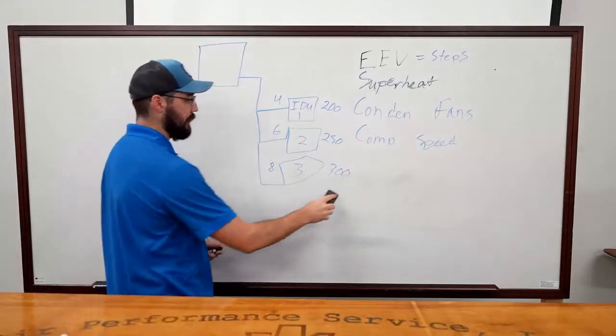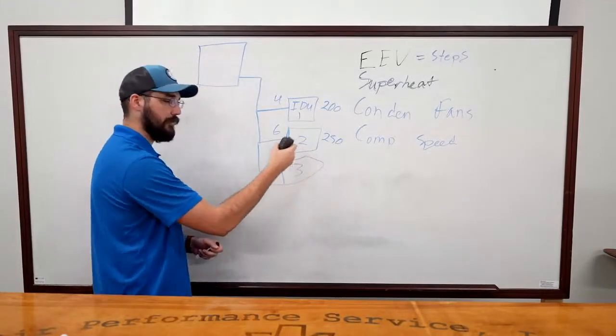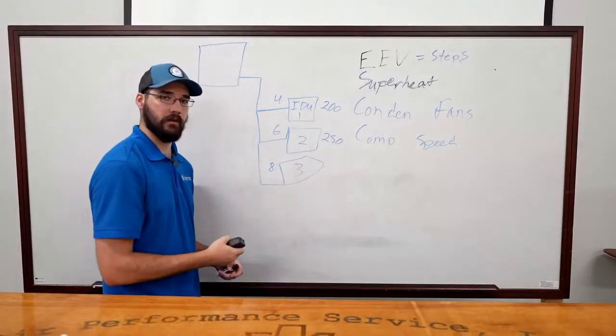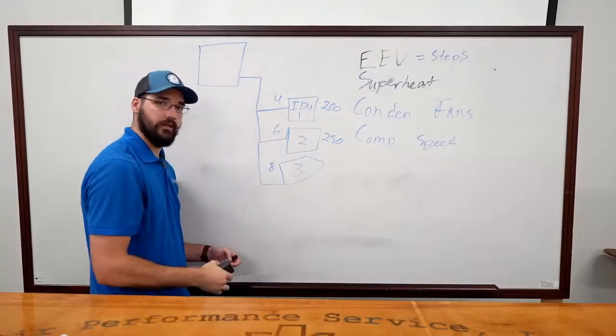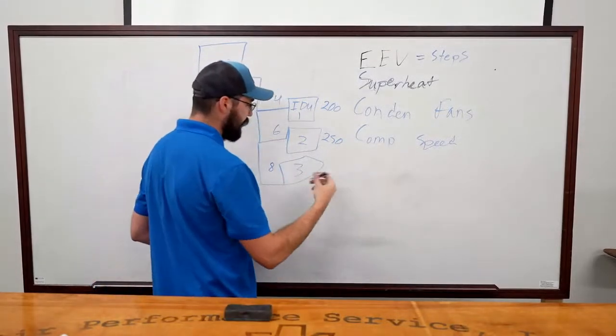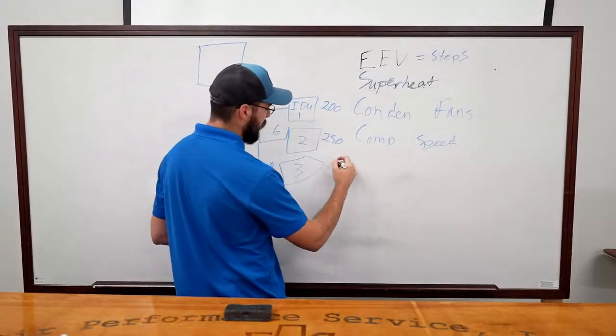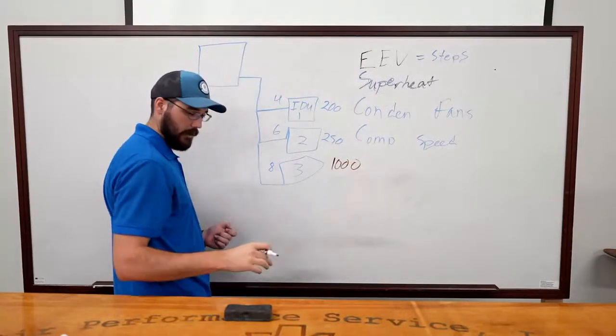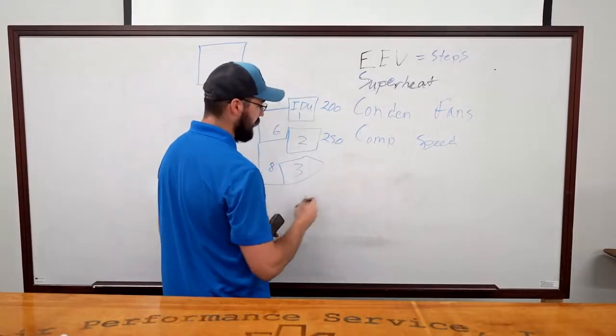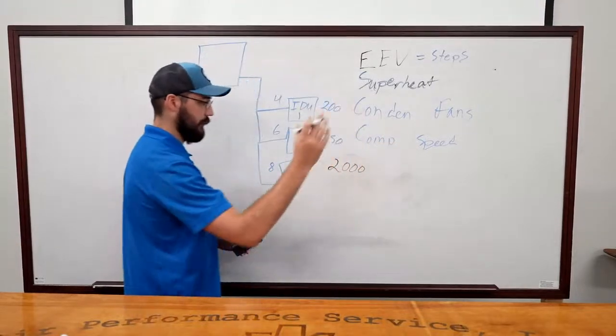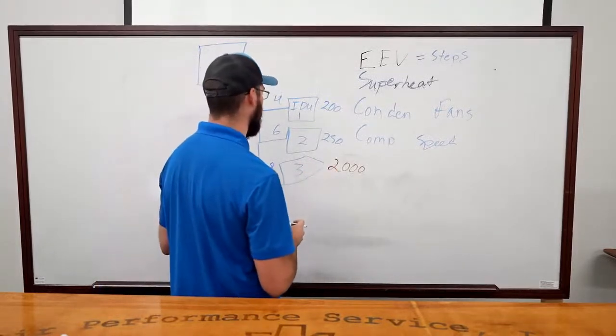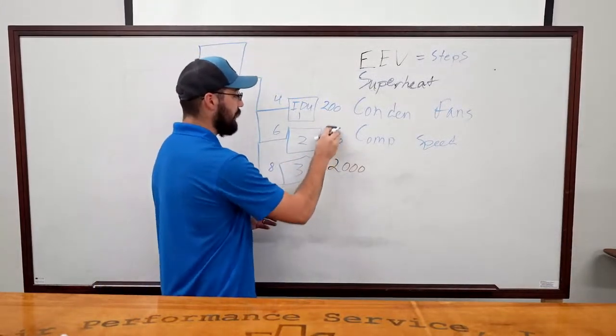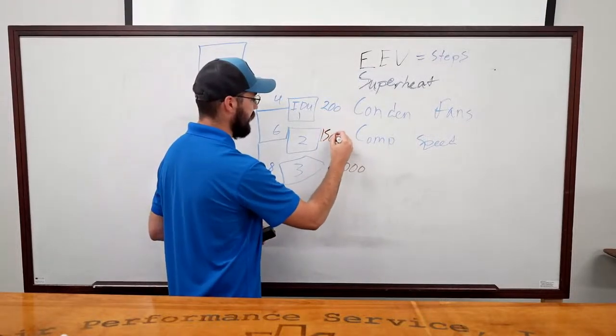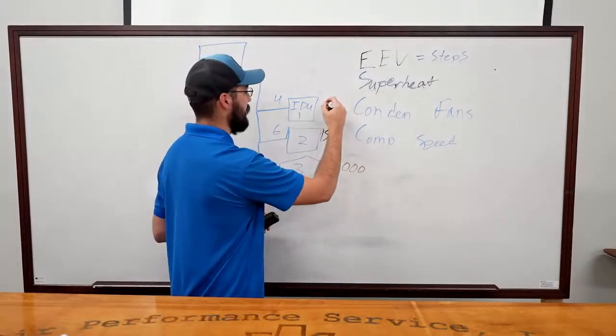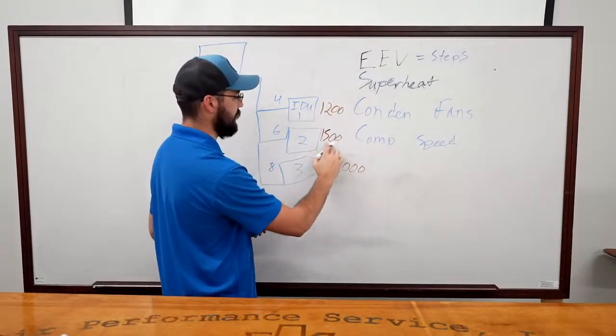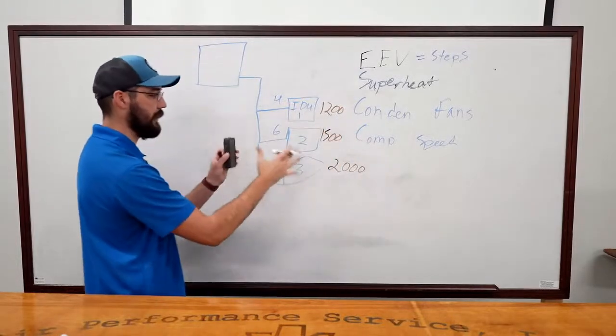And number 3 here will be the first one. What makes number 3 is the furthest one on the piping run. Number 1 would be the closest to the outdoor units, 3 the furthest. So after 30 minutes, or say at 10 minutes, we were up to 1,000 steps. All right, we give it another 20 minutes. By 20 minutes in, we're at 2,000, or say 1,950, whatever it says at the time. I rarely see them actually hit 2,000. And the rest of these, this one may be 1,500 steps, and number 1 may be sitting at 1,200, or maybe this is 1,750 and this is 1,500, whatever the case may be.